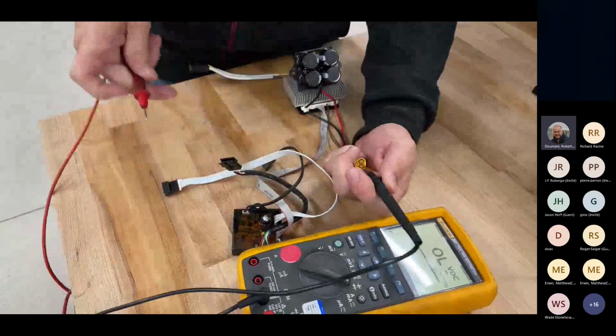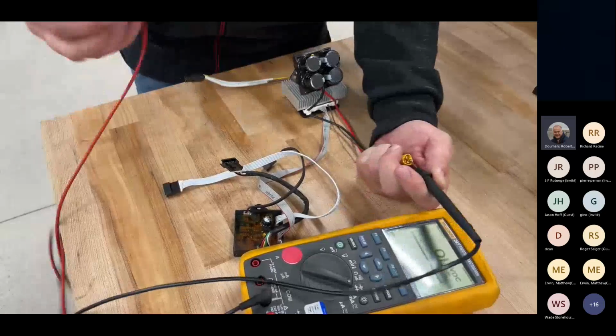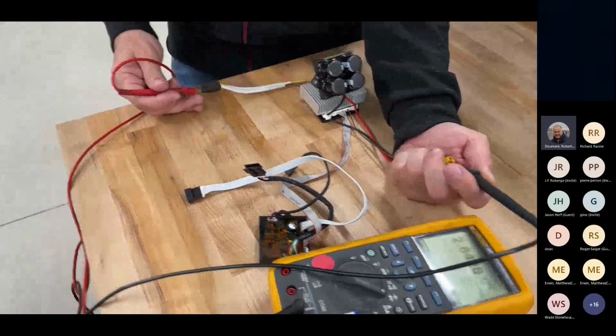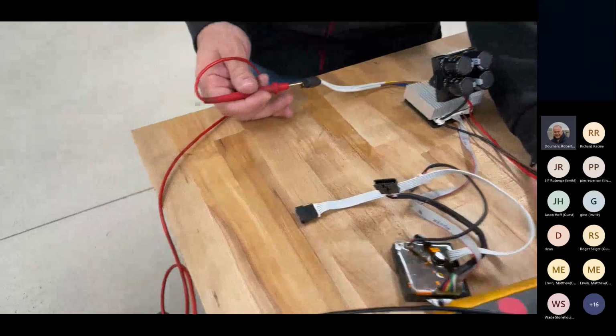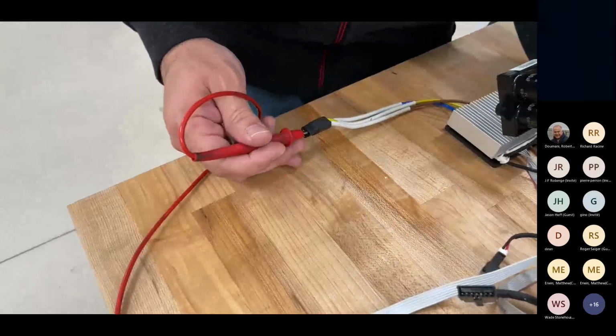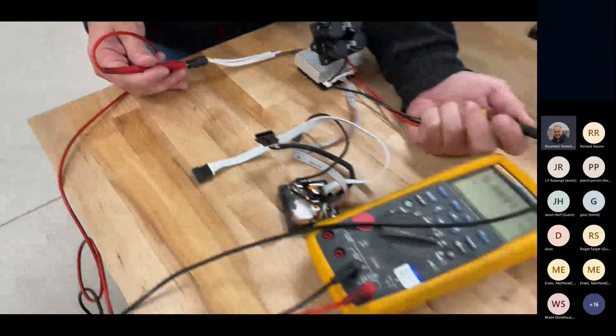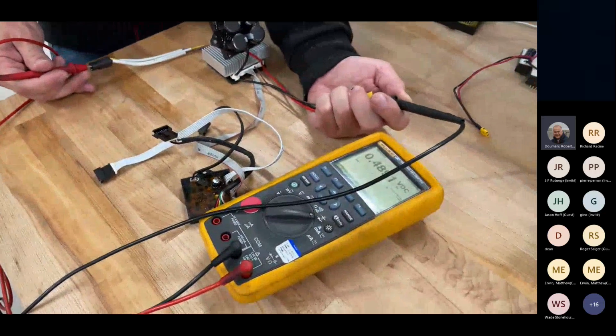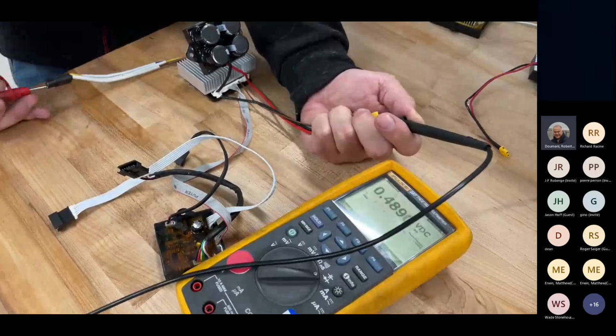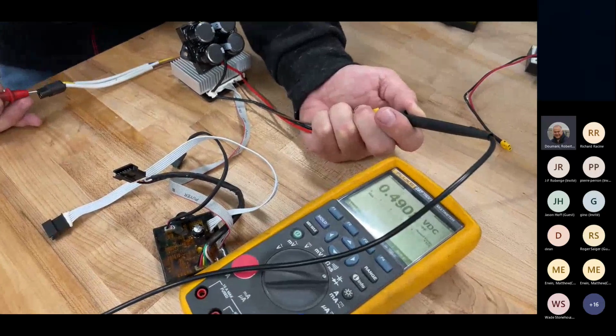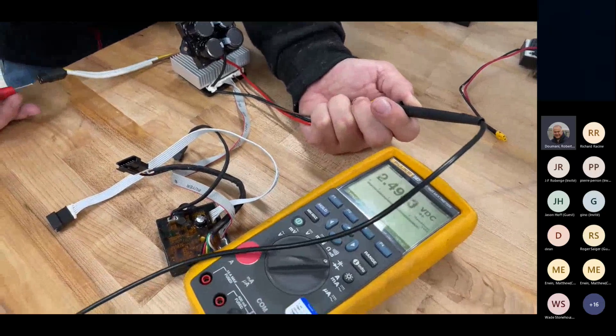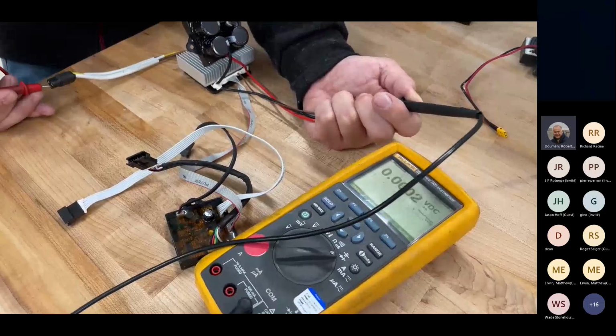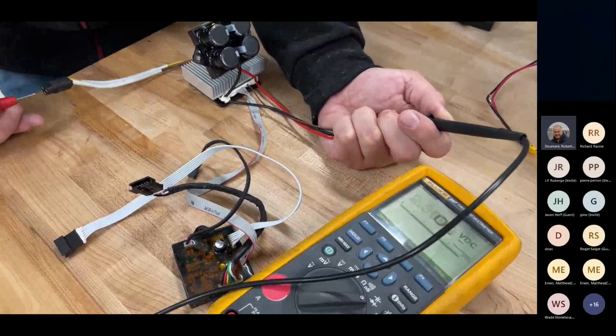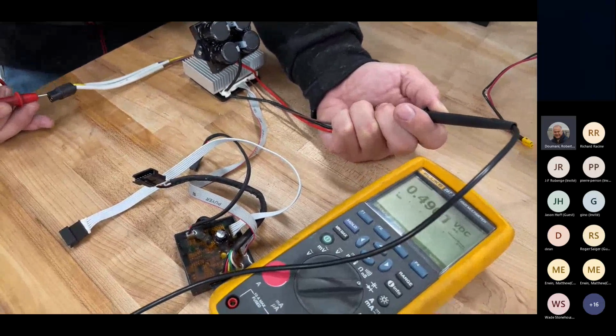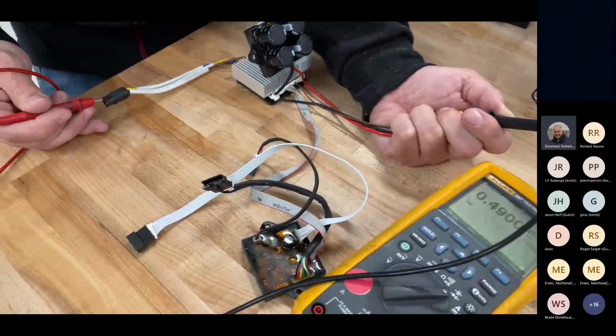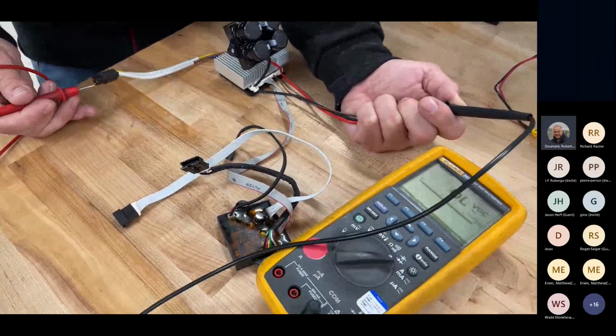Make sure you're only touching the negative lead, then touch each phase on the way out. You should have between 0.45 and 0.550 volts. And just so you see, there's one more phase, and this phase is out. You can see this is a good solid test, showing right in between the two values.